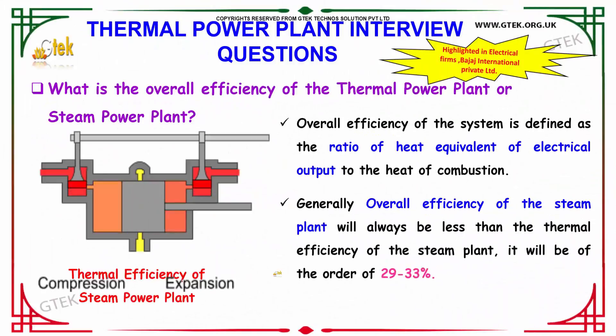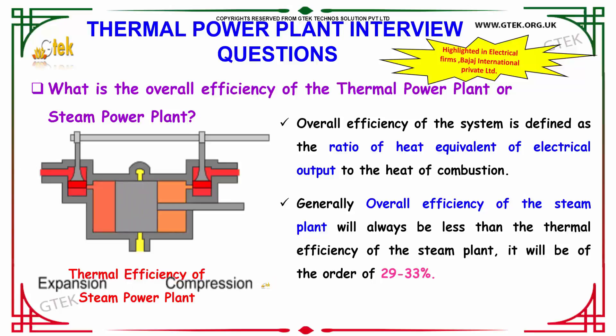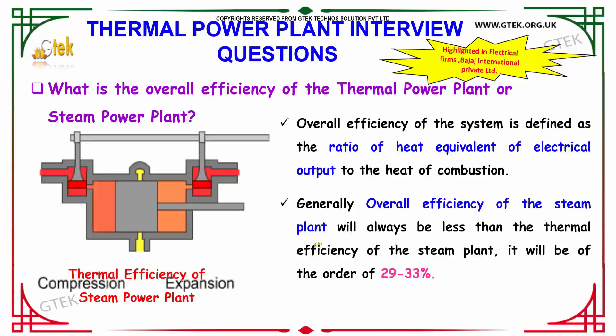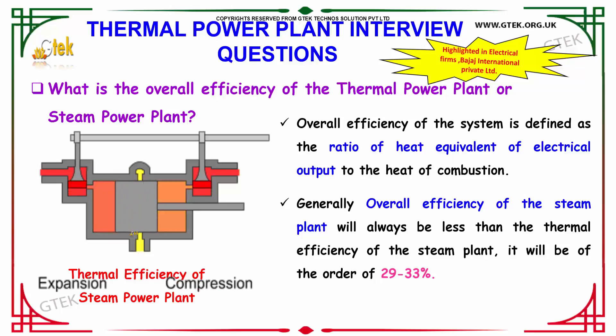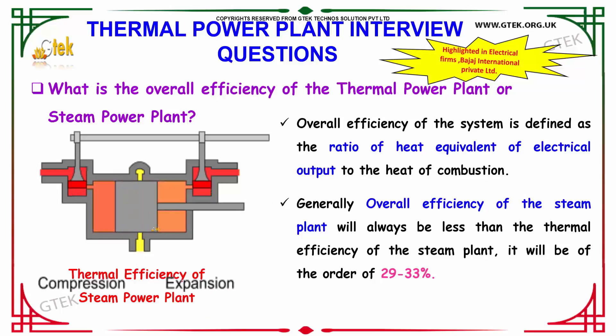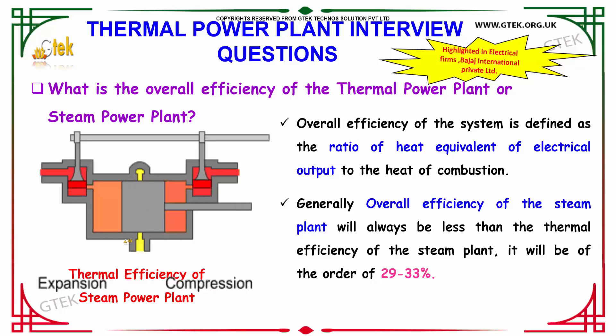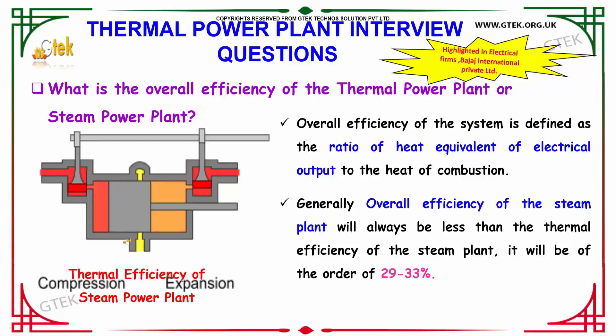What is the overall efficiency of the thermal power plant, or steam power plant? The overall efficiency of the system is defined as the ratio of heat equivalent of the electrical output to the heat of combustion. Generally, the overall efficiency of the steam power plant tends to always be less than the thermal efficiency of the steam plant, at the order of 29 to 33%.